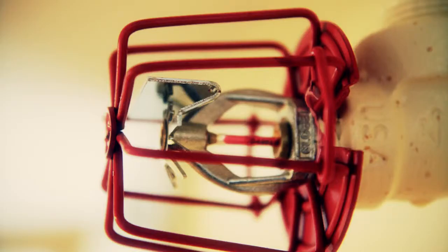In most occupancies that are assemblies, the churches, the bars, the restaurants, you get over 100 occupants, and at 100 occupants that triggers the installation of a sprinkler system. Typically, we want all of our schools to be protected. So we're always going to require, at a minimum, notification alarms so people can get out, and all new schools are required to have full sprinkler systems.